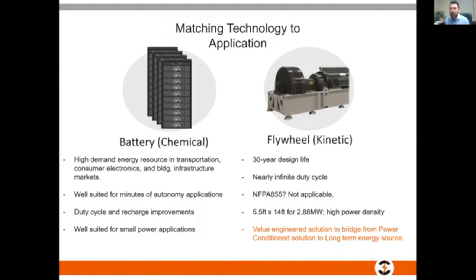Fundamentally, the flywheel has no electronics. It's just a moving wheel. There's not much obsolescence. There's not much there that can limit its life. It's incredibly reliable. It just sits there and it just spins. It has nearly infinite duty cycle. By that, we mean if there are lightning strikes, if there are multiple charges or discharge events, it doesn't affect the life because it's a flywheel. So if we use that flywheel multiple times, there's nothing there that can stop it.